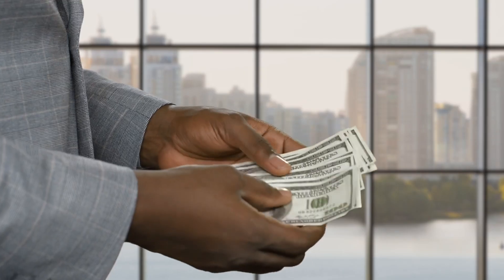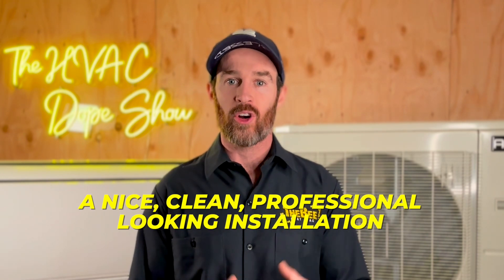My general thought is that if you're looking for a system to DIY, this is something you can do — just make sure you or someone you know is comfortable installing it. They have very affordable prices and are competitive with other brands. One thing to note is these don't come with pre-charged line sets, so you will still have to pull a vacuum when you install it. Pre-charged line sets are not ideal in my opinion — Mr. Cool owns the patent on those, and the downside is you can't shorten the line set when it's pre-charged to the exact length you need. The ACIQ product uses a traditional flaring method, which means you can make the lines the exact length you want for a clean, professional-looking installation.